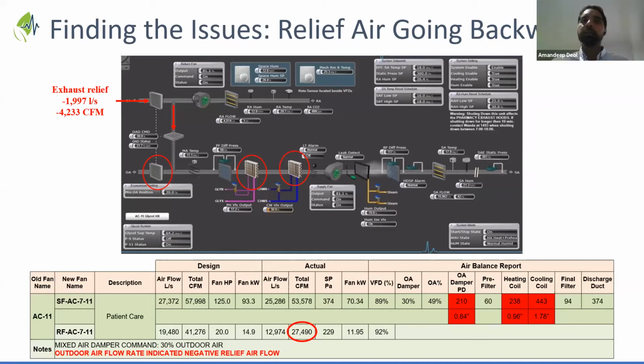So exactly that. The amount of outside air you bring into the system is directly dependent on your return fan and the supply fan. So if you don't have the right differential, regardless of the damper position, it's going to bring that amount of outside air into the building anyway.